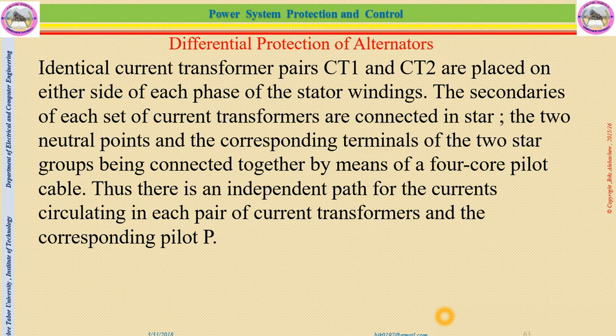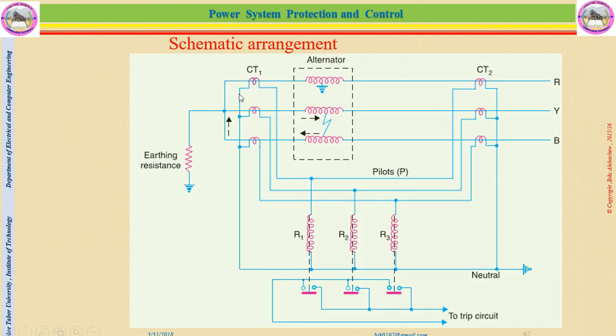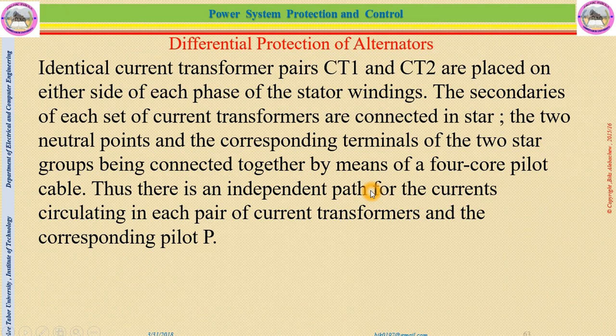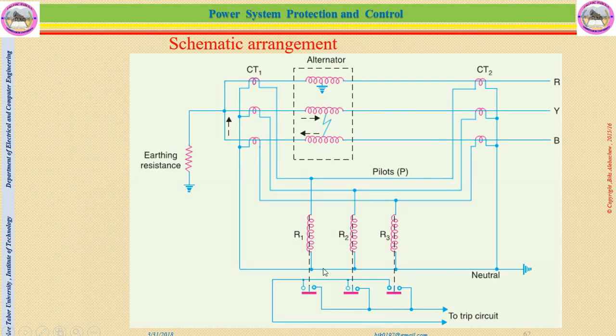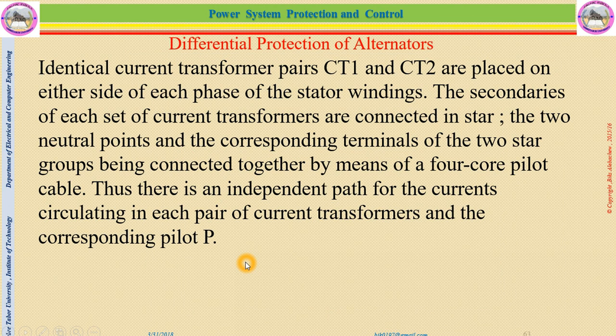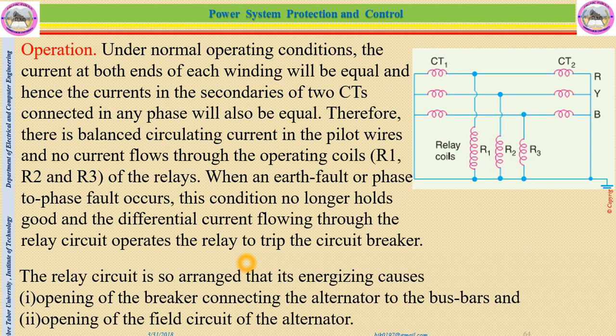Now, differential protection of alternator principles. Let us see. Identical current transformer pairs, CT1 and CT2, are placed on either side of each phase of the stator winding. The secondaries of each set of current transformers are connected in a star, as I show in this diagram. The two neutral points and the corresponding terminals of the two star groups are connected together by means of a 4-core pilot cable. You can see here they are connected in a star connection with the fourth pilot wire, which is called the neutral wire. Thus, there is an independent path for the current circulating in each pair of current transformers and the corresponding pilot wire. Now, what will be the operation?